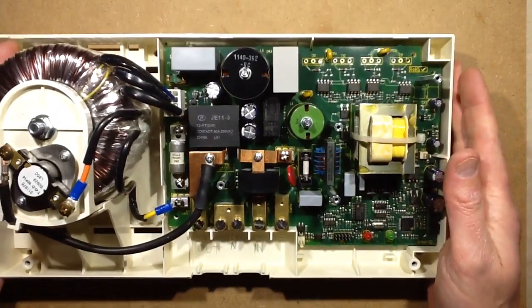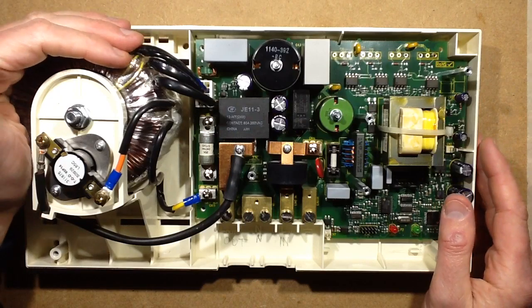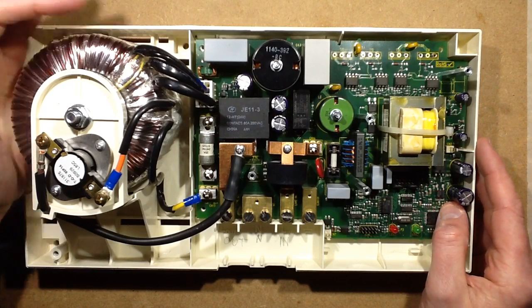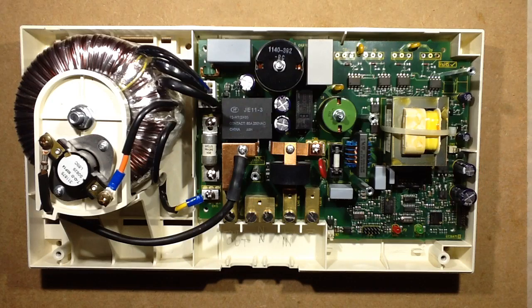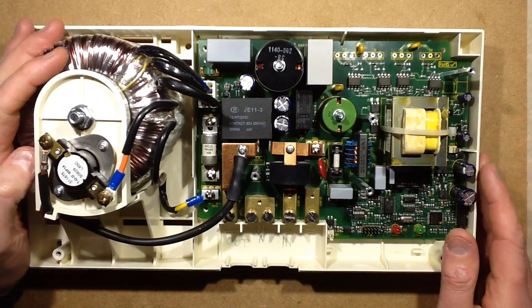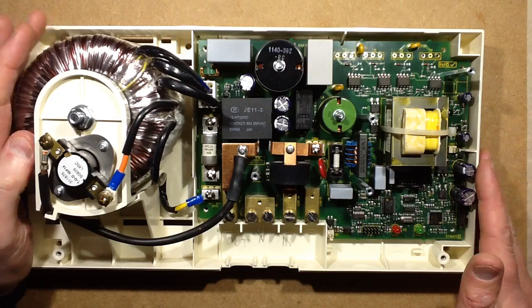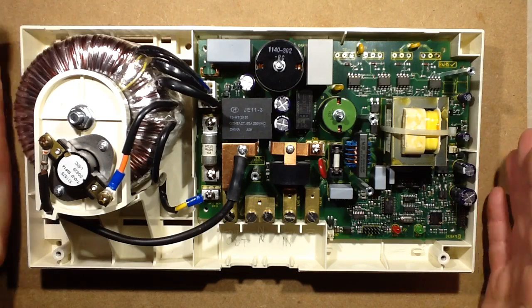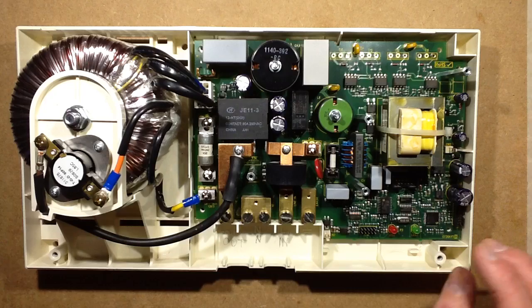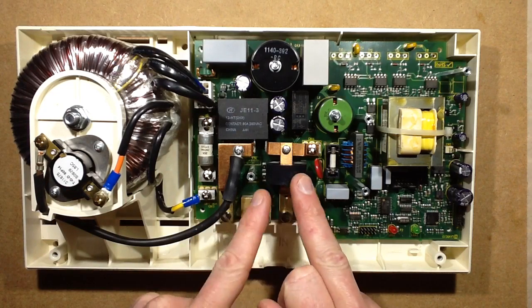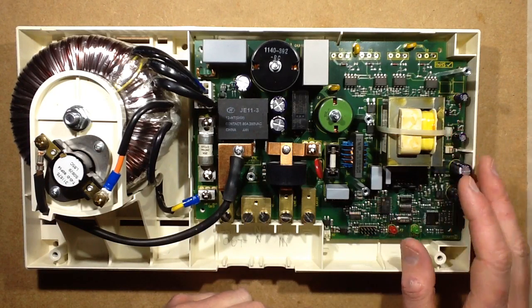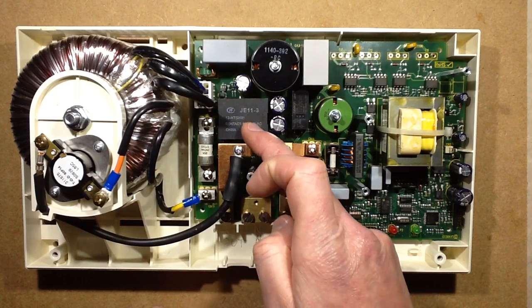And that's a bit odd because, if I move this out the way now, this thing is actually rated for a continuous load of just 8 amps, which isn't a lot. Even with our 240 volt supply, that's not a lot. That's 2 kilowatts. And it's got a peak rating, a short duty cycle rating in bursts, of 20 amps. And if the transformer starts getting too hot, if the load's really high, it will bypass the transformer, and it's got a current sensing coil here that feeds this excessively complicated circuitry. And this thing here is an 80 amp bypass relay.